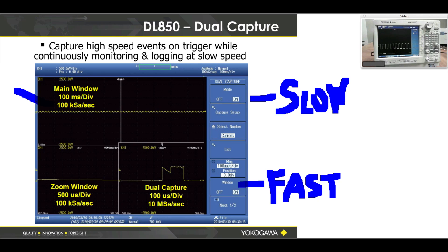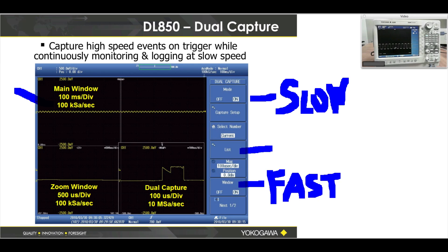When you open a dual capture waveform in X-Viewer, it will have all of these events, and also in this list here you could have a thousand events or five thousand events, each saved as a separate acquisition because each of those events met a criteria such as a surge. That really is all dual capture is — it captures simultaneously at a slow speed, and then when it has events, it samples at a much higher rate.